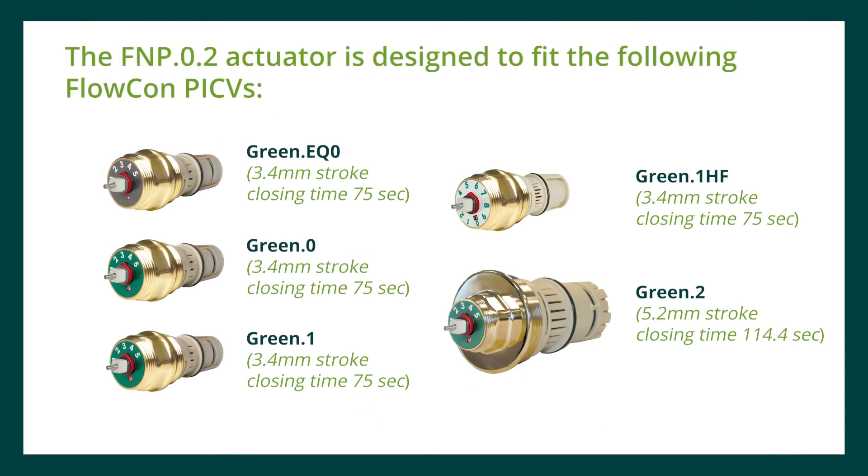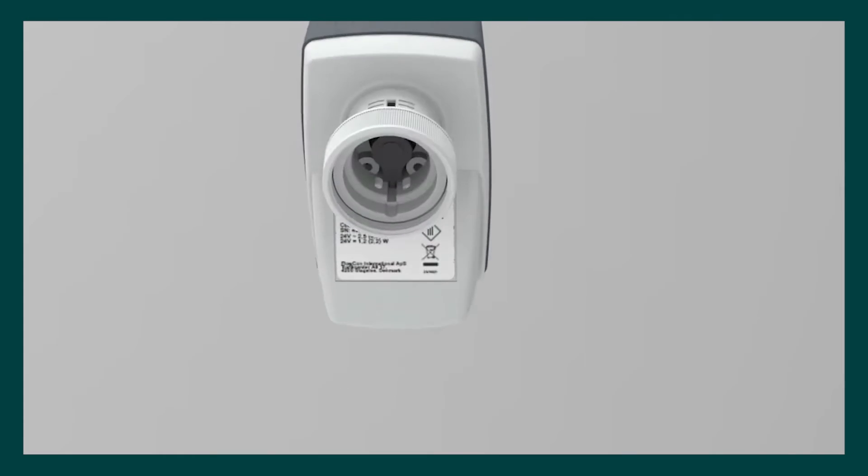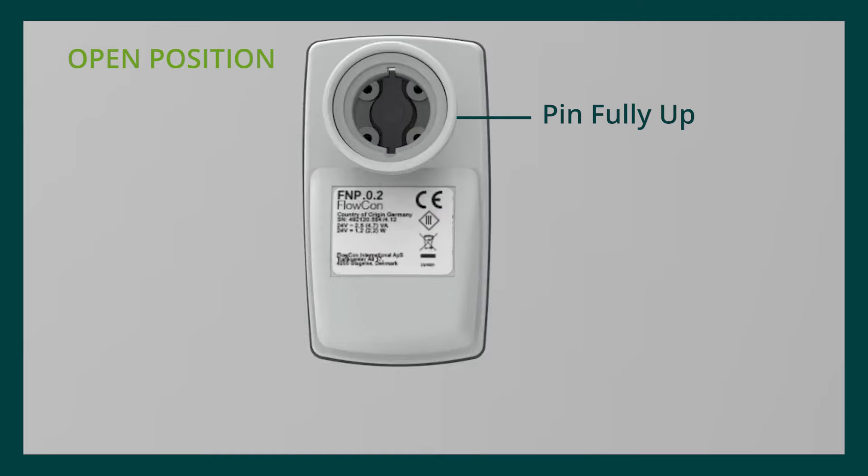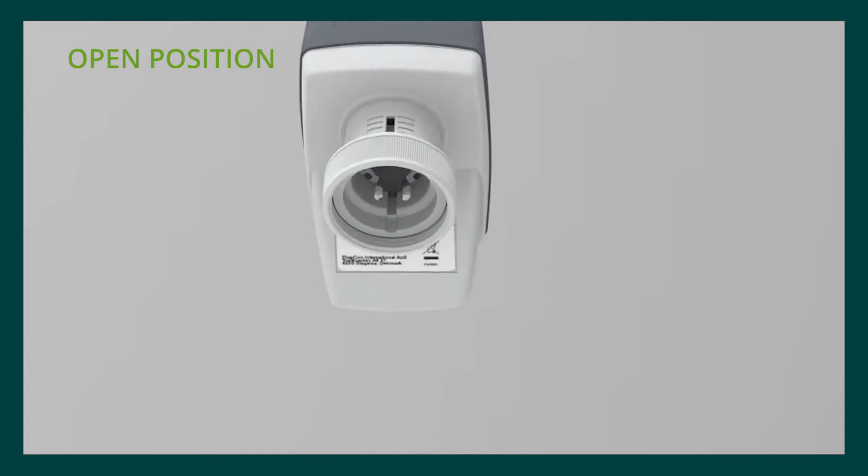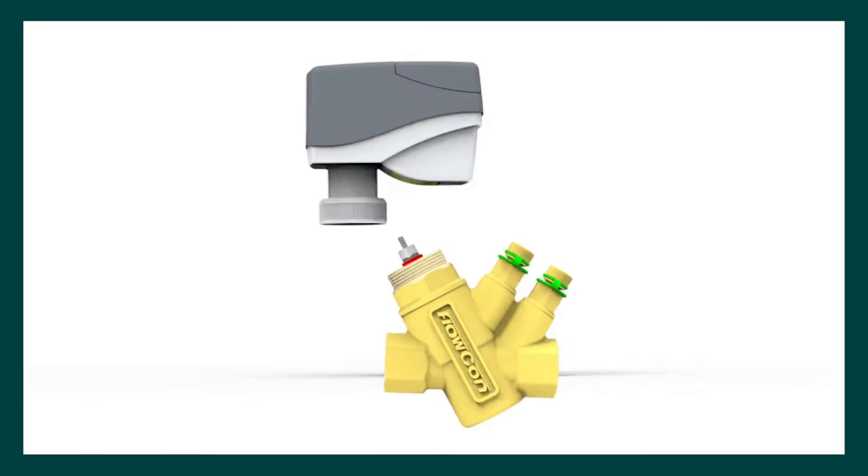The FNP0.2 actuator is designed to fit the following Flowcon PICVs. Ensure the actuator is in the fully open position before mounting it on the valve to avoid the risk of damaging the PICV. Align the actuator to the PICV threaded insert.